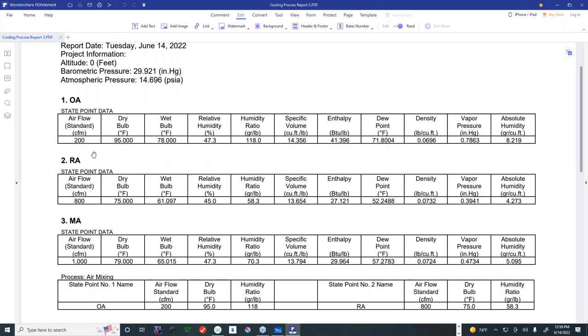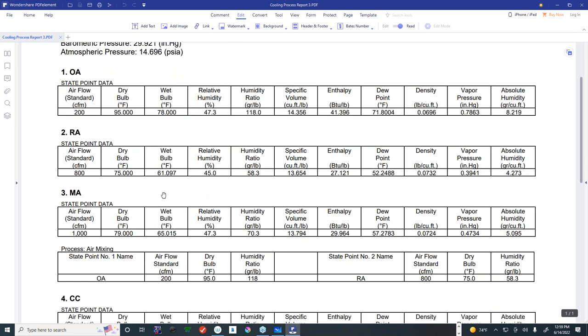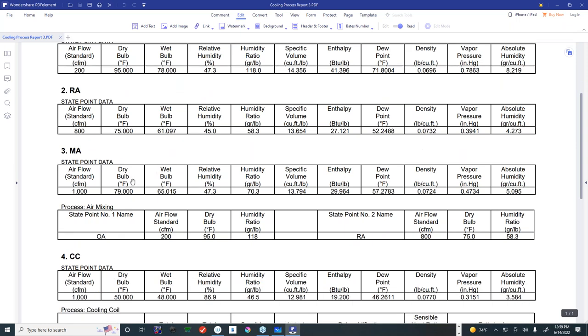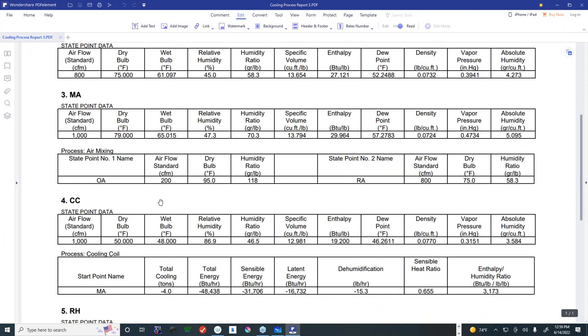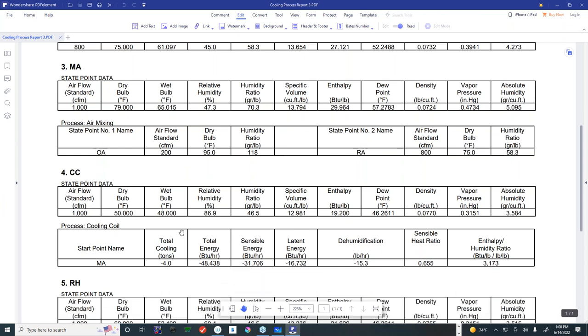I see my hand. Okay, so there's the outside condition, there's the return air condition, and then there's the mix air. When those two quantities mix at 200 CFM and 800 CFM, the mix air temperature is down here, 79 degrees, we calculated that earlier. And then it goes through the cooling coil, enters the cooling coil at 79 degrees dry bulb and 65.015 wet bulb, and leaves the cooling coil at 50 degrees dry bulb and 48 degrees wet bulb. A little different set of conditions, but you can get the general idea.